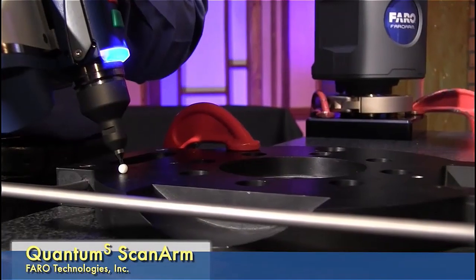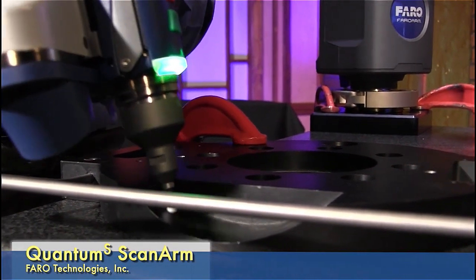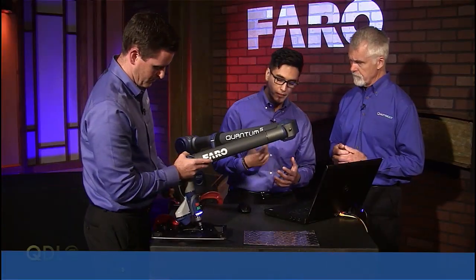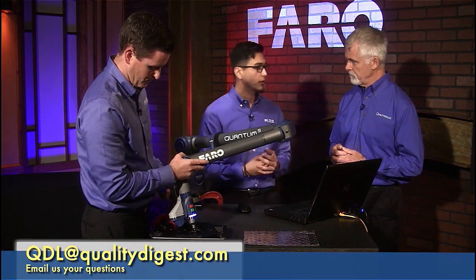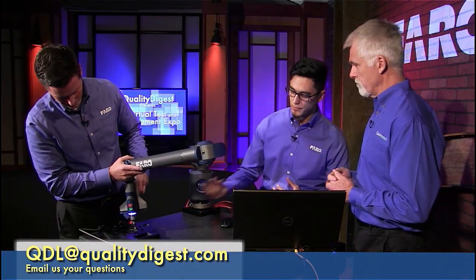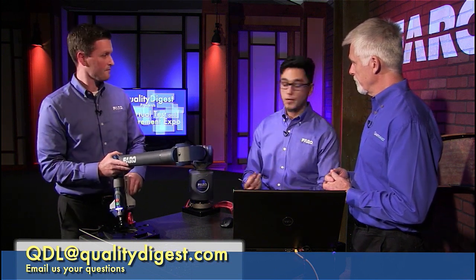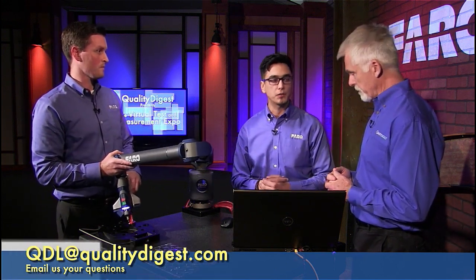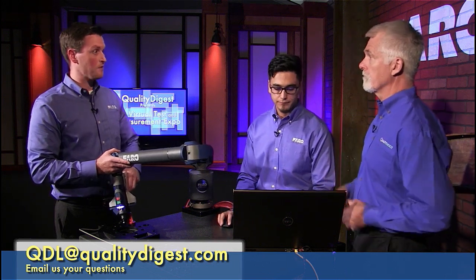Okay, and tell us a little bit about probe calibration. Right, so the probe, you need to calibrate it the first time you use it. That's the beauty of the Quantum S. It's going to remember the calibration for that specific probe, for that 3 and 6mm probe. So you can swap those very rapidly without needing to recalibrate each time you swap. So that'll make it nicer and faster for an operator to get their inspection done quicker. Sure. Yeah. They can just put the probe in. The electronics recognize the probe, right, and then it loads the appropriate calibration information for it.